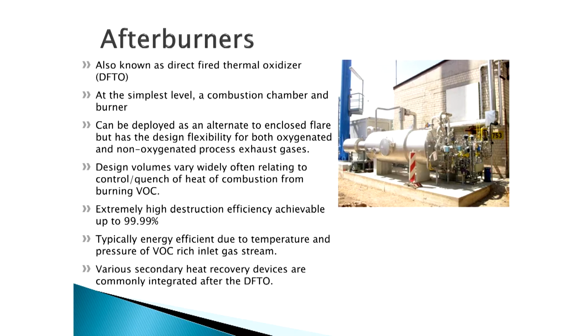We may have a refractory lined chamber. The design volume varies widely in these applications. The important feature of these applications is that we can achieve super high destruction efficiencies when they're designed properly. We can get up to 4 nines and better in many cases. They're very energy efficient, from the standpoint that we typically have very high heat loads in these systems, and we can then deploy other devices behind them to recover that energy, generate power, and so on and so forth.